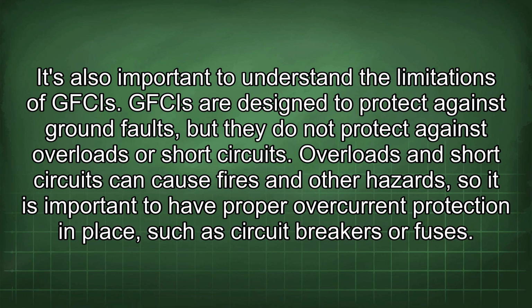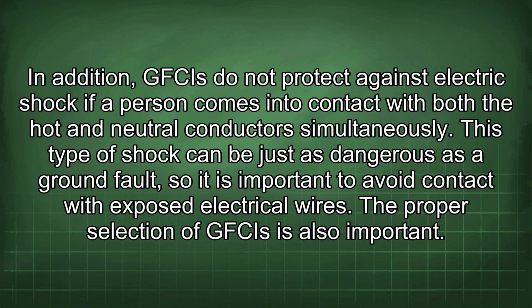GFCIs are designed to protect against ground faults, but they do not protect against overloads or short circuits. Overloads and short circuits can cause fires and other hazards, so it is important to have proper overcurrent protection in place, such as circuit breakers or fuses. In addition, GFCIs do not protect against electric shock if a person comes into contact with both the hot and neutral conductors simultaneously. This type of shock can be just as dangerous as a ground fault, so it is important to avoid contact with exposed electrical wires.